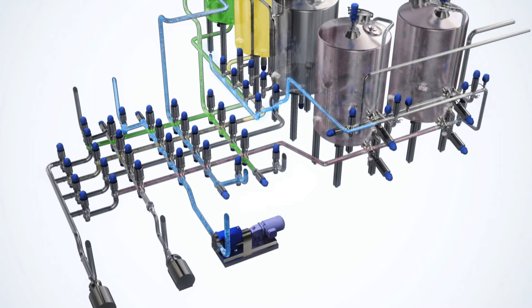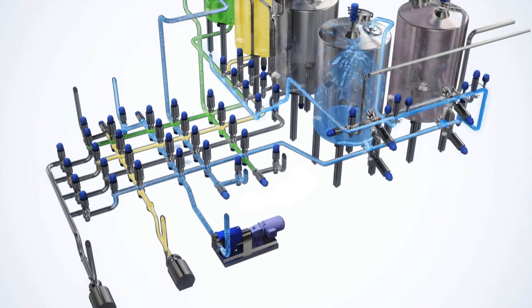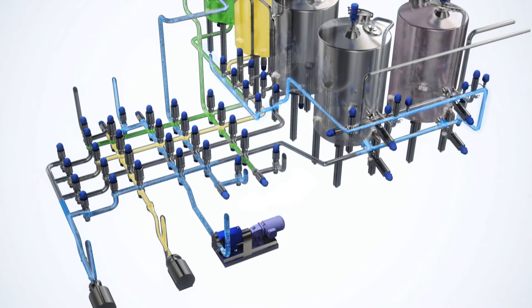To optimize the valve matrix design, it is important to consider factors such as the complexity of flow management, product viscosity, type of process, product and CIP sequences that are run, and placement of the pump before or after the valve matrix.